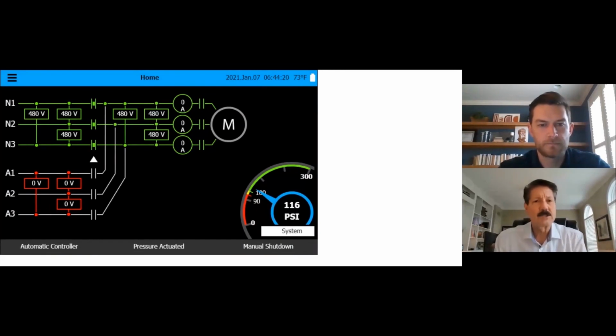We like color graphics. You can look at one screen and look at the complete system and what's going on with that system. Is it operating? Is it not? Is it emergency power? Is it not? The system pressures, and you get a read. You know, technology has really improved. A lot of the other manufacturers in the industry have followed suit with color screens also. Maybe not as interactive, but I think it's great because technology has moved forward in our industry. We're very conservative when it comes to life safety, so moving forward, it's slow and methodical.